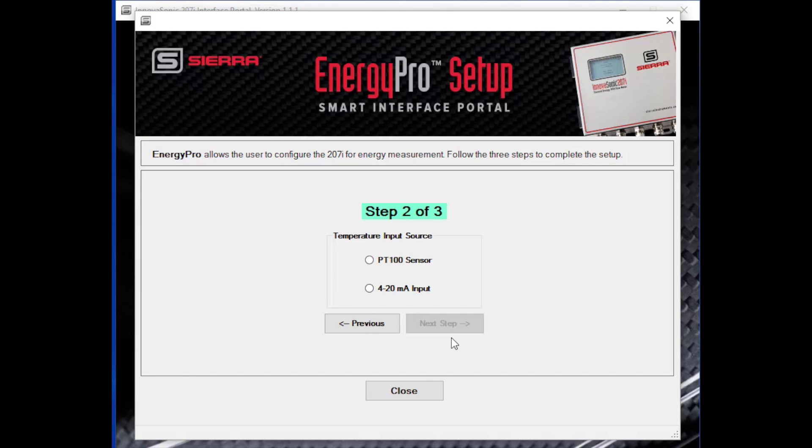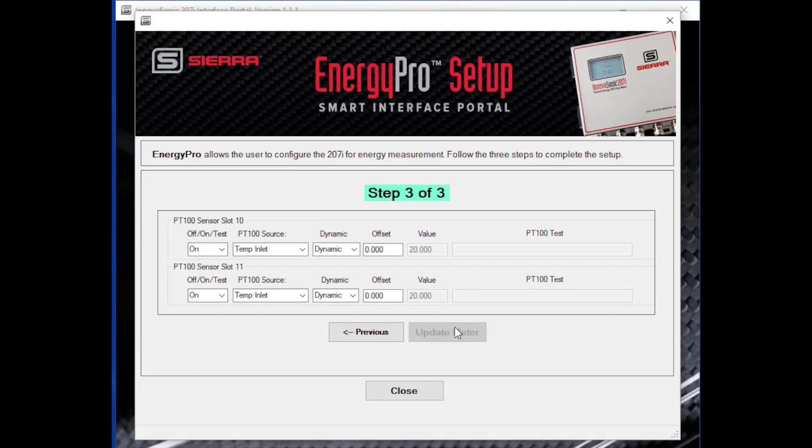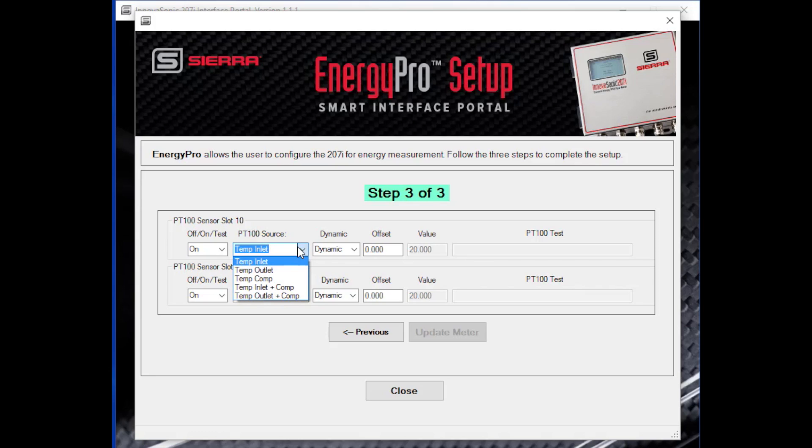Or the second choice is to use a 4 to 20 analog input. So a temperature transmitter that you can, there are various models that you can get for that. In this case, let's select a PT100. So step two is to identify that we are using PT100. And then step three is to set up the PT100 and basically tell the meter, what is this measuring? It can measure the inlet temperature and the outlet temperature. Those are the two typical measurements. So the hot leg and the cold leg. Or it can measure any combination of the two. The temperature inlet, temperature compensation temperature, various combinations of those. So you tell it what you want it to measure, you set both of those up and you're complete. You're ready to make an energy measurement.